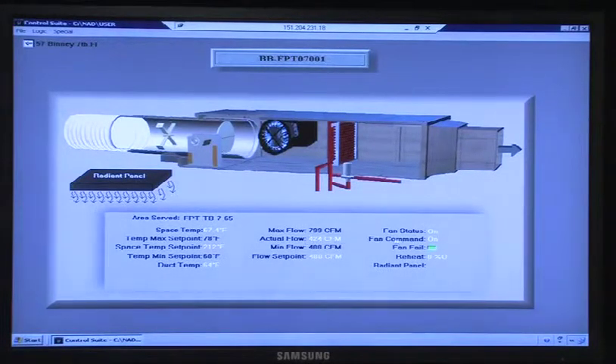So these are fan powered boxes. They certify their own HEPA filtration, just like they do downstairs in that room. So these are all fan terminal boxes serving that space. Do we have radiant panels in there? Did you catch that? Check radiant panels. All right, see, you're jumping right on us. Oh, change that. So we'll have to get rid of that radiant panel. So, fan terminal boxes serving the space. And make sure we really understand the area: it's the pharmacy. It's considered a compound, a prep, drug IV prep room. I think it's considered an IV prep room.